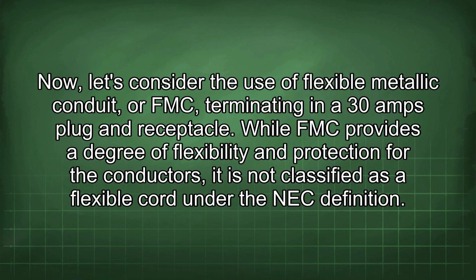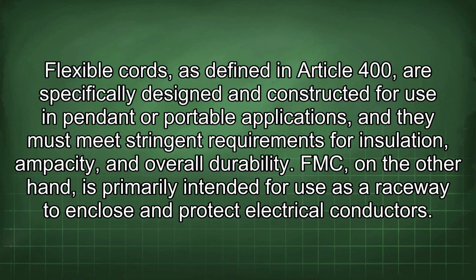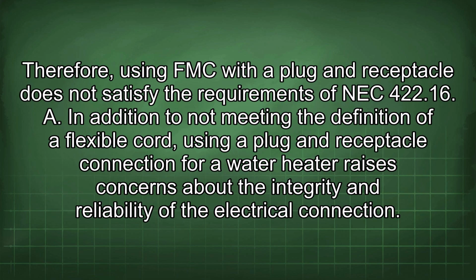Now, let's consider the use of flexible metallic conduit, or FMC, terminating in a 30 amps plug and receptacle. While FMC provides a degree of flexibility and protection for the conductors, it is not classified as a flexible cord under the NEC definition. Flexible cords, as defined in Article 400, are specifically designed and constructed for use in pendant or portable applications, and they must meet stringent requirements for insulation, ampacity, and overall durability. FMC, on the other hand, is primarily intended for use as a raceway to enclose and protect electrical conductors.